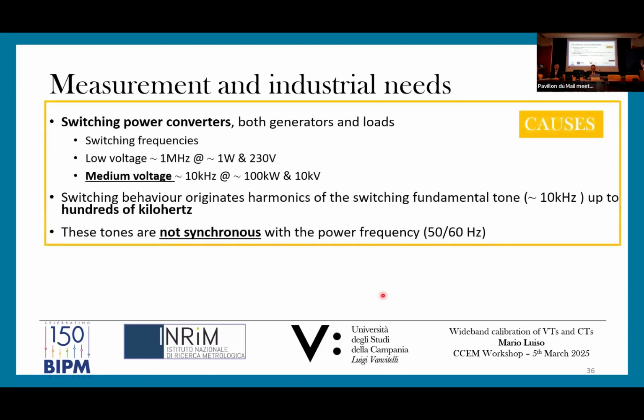From measurement and industrial points of view, what are the needs? Switching power converters nowadays can be directly connected to medium voltage, and they can have a switching frequency in the order of tens of kilohertz, power in the order of tens of kilowatts, and voltage in the order of tens of kilovolts. So the switching frequency behavior originates harmonics of the switching fundamental tone up to hundreds of kilohertz. They are not harmonics of the 50 hertz. This is why I don't like very much the term supraharmonics, because it is quite confusing. They are harmonics, but not harmonics of the 50 hertz. They are harmonics of the tones around the switching frequency. In fact, these tones typically are not synchronous with the power frequency.